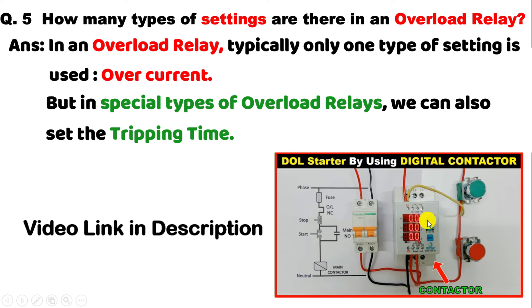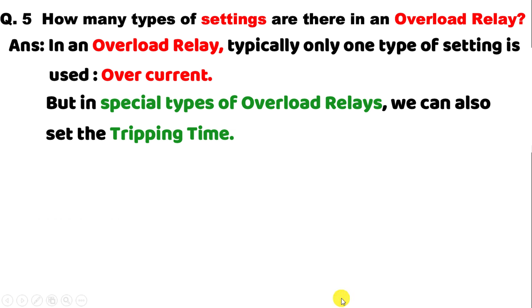For where the option to set time is in an overload relay — I already made a video on this. In that video you saw a digital contactor, in which an overload relay was inbuilt, with two knobs to set overcurrent and time. But it's not only in digital contactors — in special normal overload relays also you get two options. So the answer is: normal overload relay gives one option to set overcurrent, but special type of overload relay allows setting tripping time as well. Click on the right-hand side video to learn about digital contactors.